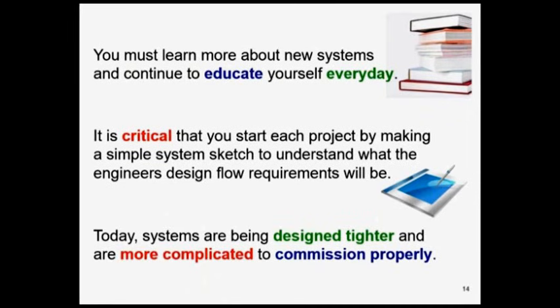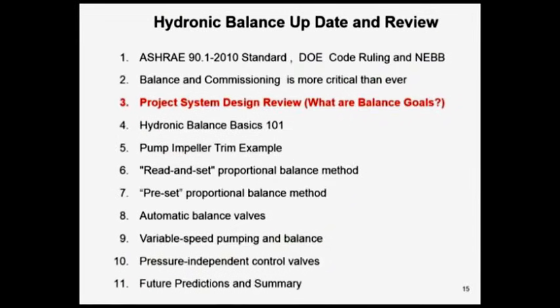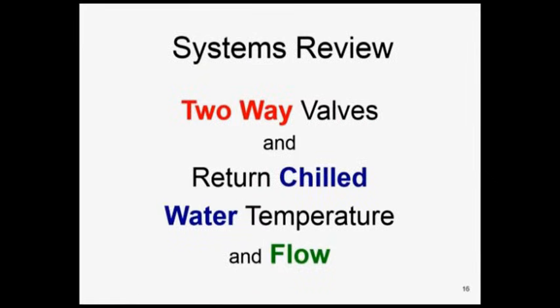Last but not least, we're going to have tighter pump heads, tighter cooling loads. We're not going to have the old fat we used to have, so we have to make sure we do these things right, because the systems are being designed tighter and tighter to get less and less energy usage. At the same time, some of the controls are getting more complicated. So it's more critical than ever that you understand what your system looks like and what it is. So let's look at some typical systems and ask what your balancing goals might be.